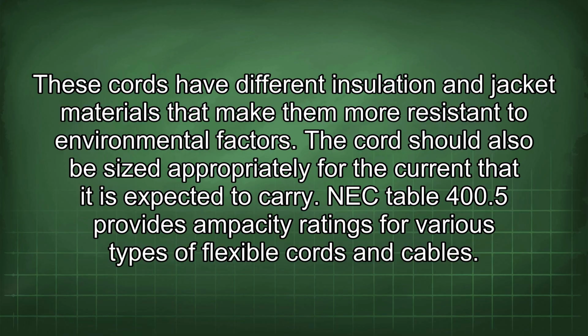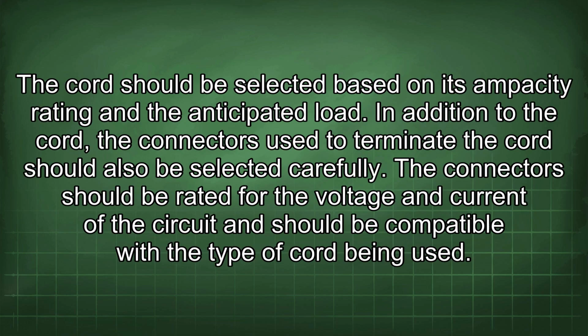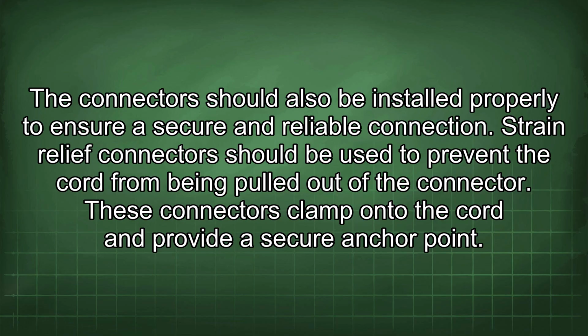The cord should also be sized appropriately for the current that it is expected to carry. NEC Table 400.5 provides ampacity ratings for various types of flexible cords and cables. The cord should be selected based on its ampacity rating and the anticipated load. In addition to the cord, the connectors used to terminate the cord should also be selected carefully. The connectors should be rated for the voltage and current of the circuit and should be compatible with the type of cord being used. The connectors should also be installed properly to ensure a secure and reliable connection. Strain relief connectors should be used to prevent the cord from being pulled out of the connector. These connectors clamp onto the cord and provide a secure anchor point.